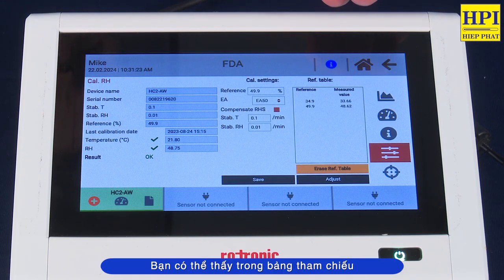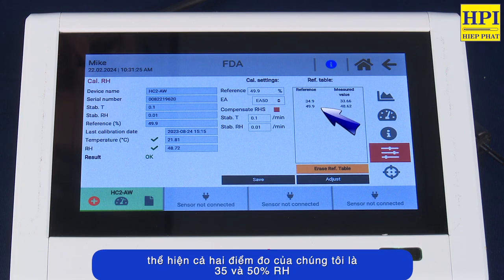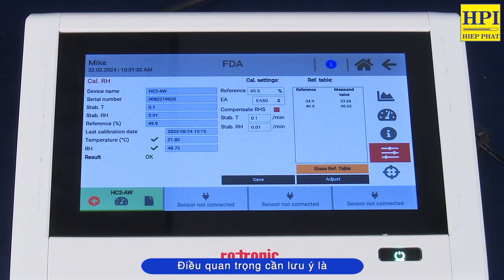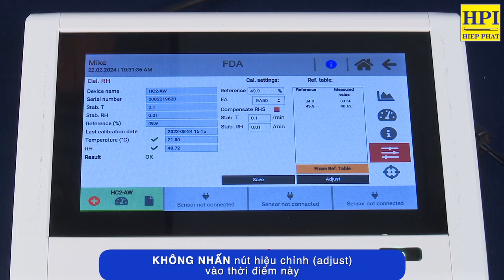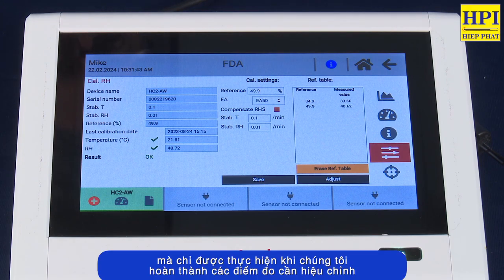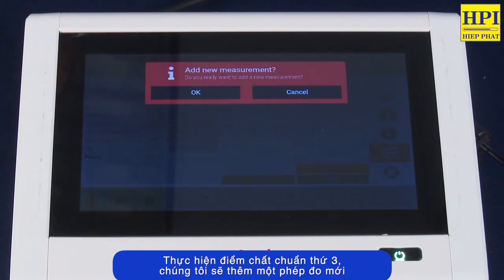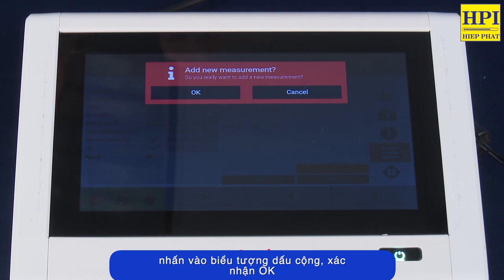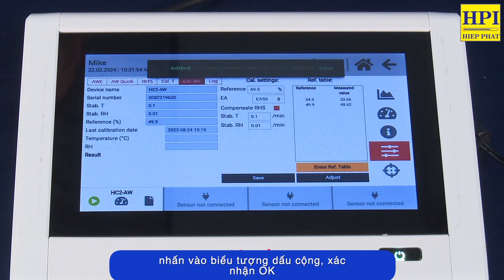And as you can see in the reference table now, it indicates both of our measurement points, the 35 and the 50% RH. From here, we want to complete with our third humidity standard. And it's important to note we do not hit the adjust button at this point. It is only until we've completed the number of measurement points that we will adjust. We will add an additional measurement point, again with the orange plus icon, and confirm OK.